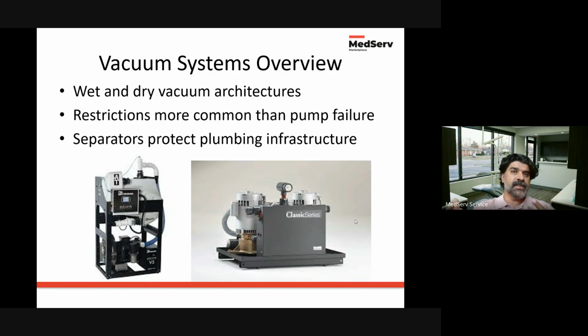The one thing to note though is that this one system usually is supporting the entire facility itself. So you have multiple operatories that are relying on this one piece of equipment. And so if this doesn't perform properly, they're losing opportunity to work on different dental chairs downstream. A lot of times, similarly to what was said before, clogged filters or traps are an issue. There's separator maintenance that needs to be done. A lot of the waste and debris that's pulled out from dental procedures have some minerals or chemicals or elements in them that aren't safe to be introduced into the wastewater stream, and those have to be separated out.